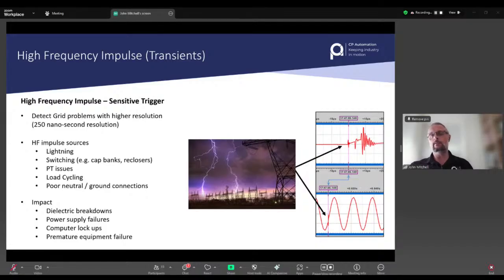Most people only think of transients coming from lightning, but the reality is 80% of transients are created within your own factory, or your customer's factory, by their own equipment. That can be switching over between generator and mains, fast-acting switching direct online, or big chillers coming on and off. There are so many other things that can cause transients within the network.